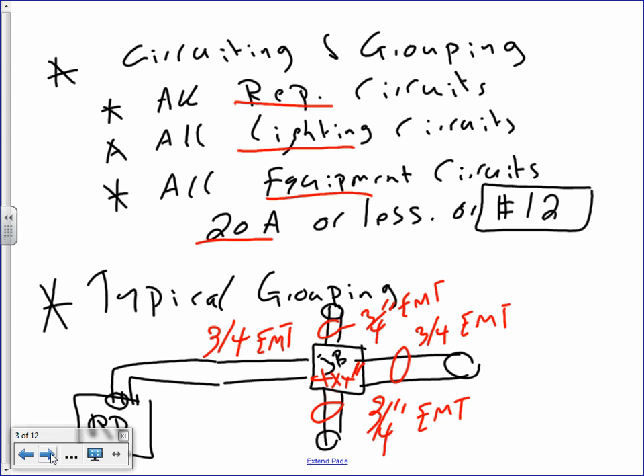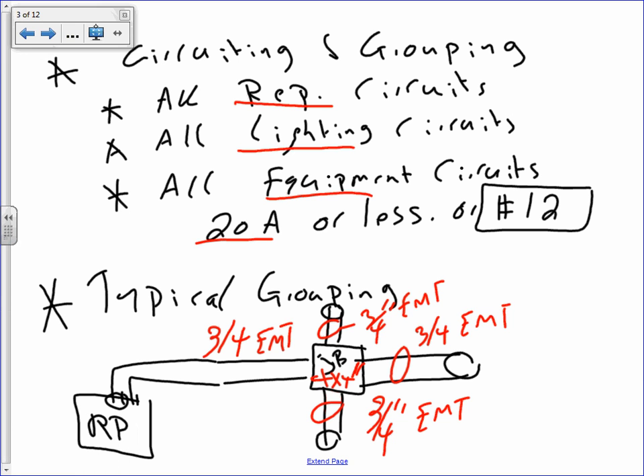Okay. Now, typical grouping. Here's a typical grouping. I showed you a typical grouping. Feel free to agree or disagree. I came from my receptacle panel, and I go into 3/4 of an inch. You don't want to put 1/2 inch. Always 3/4 of an inch, into a J box, 4x4. A deep box is a good idea. So we came out of this panel here into the ceiling, right in here.